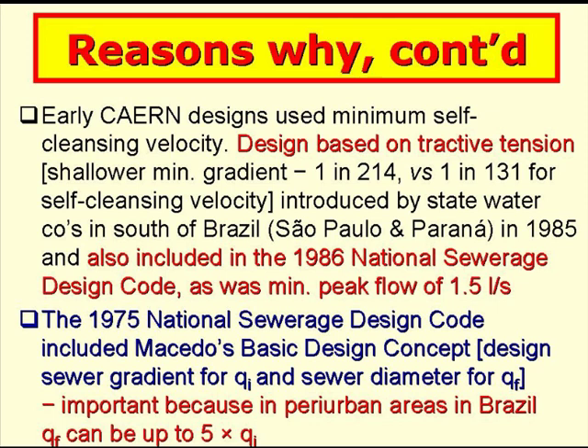The early designs by CAERN used a minimum self-cleansing velocity. The design based on a minimum tractive tension of 1 pascal was introduced by state water companies in the south of Brazil, in the states of São Paulo and Paraná in 1985, and was also included in the 1986 revision of the National Sewerage Design Code, as was the minimum peak flow of 1.5 litres per second. The 1975 version of the code had already included Macedo's basic design concept, where the sewer gradient is designed for the flow at the start of the design period and the sewer diameter for the flow at the end — important for simplified sewerage because in peri-urban areas in Brazil, QF can often be up to five times QI.